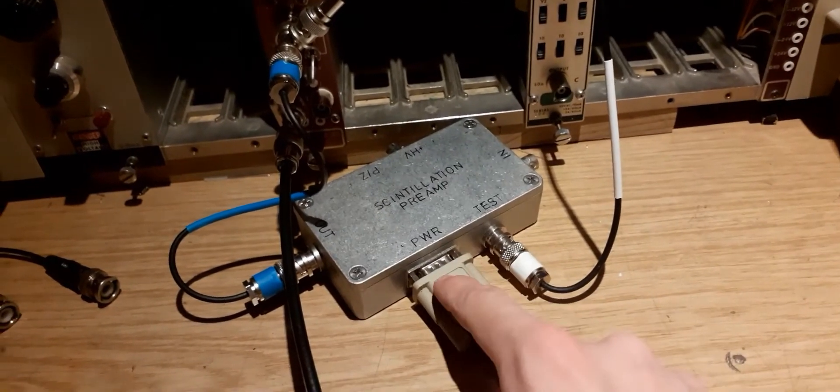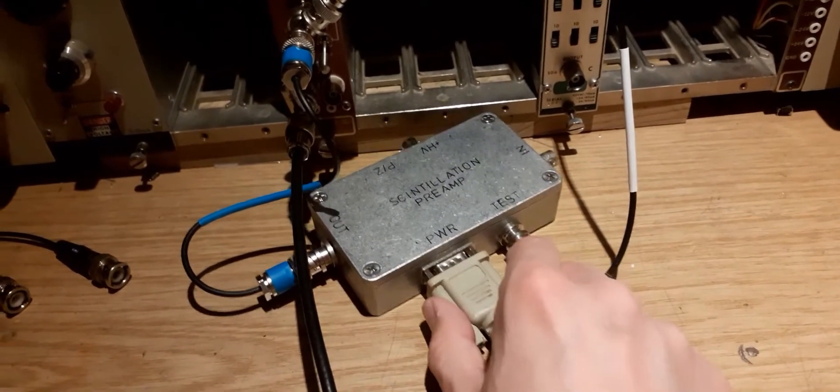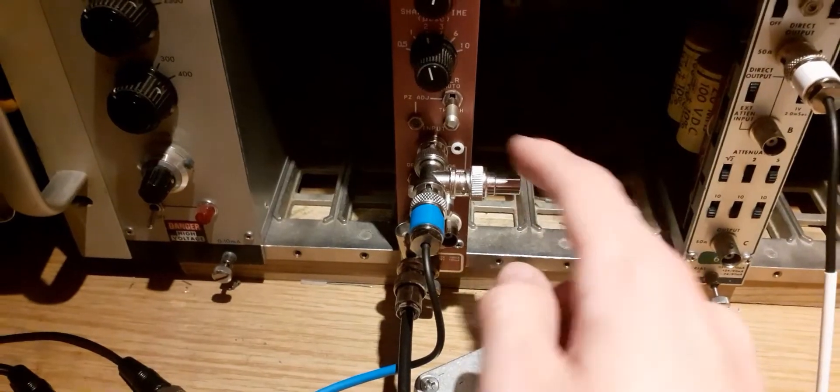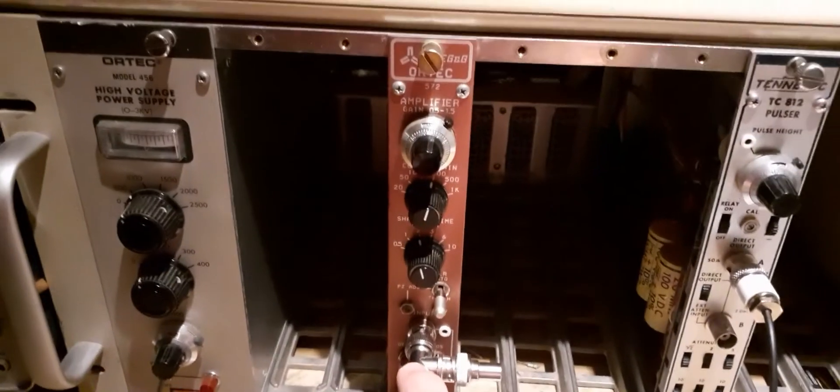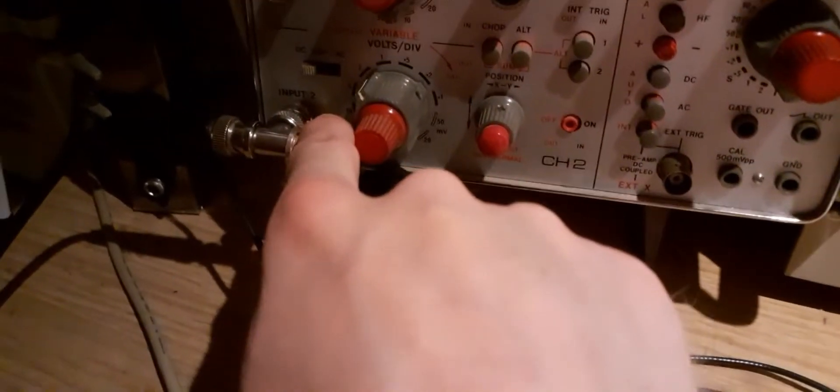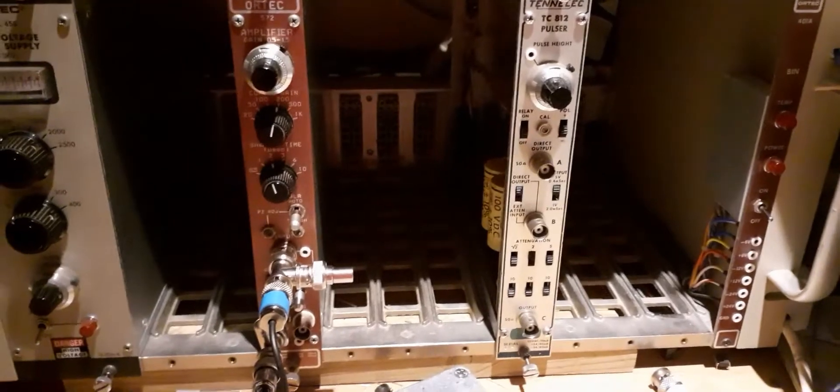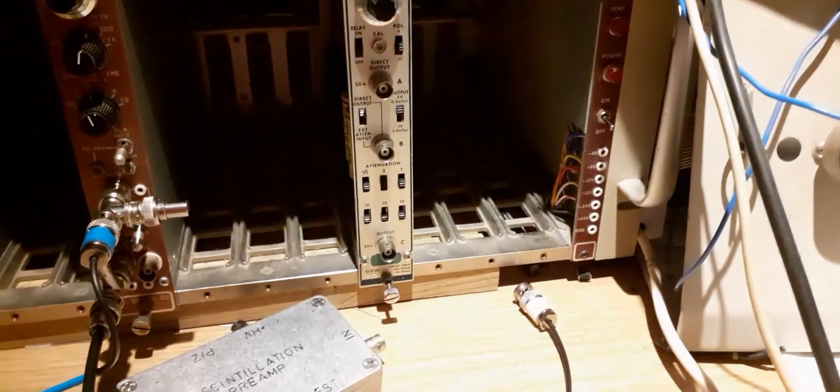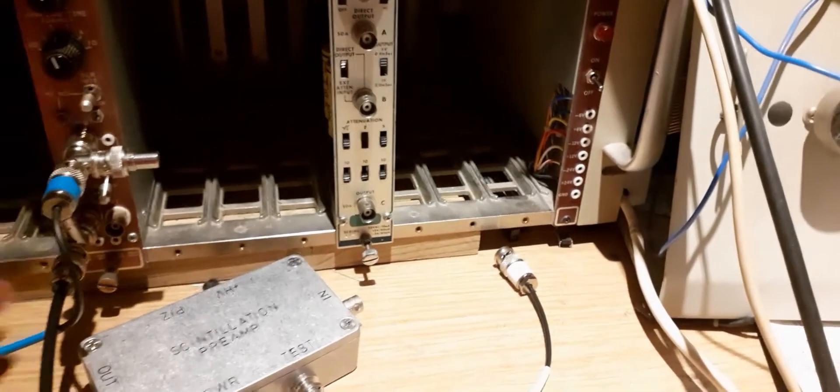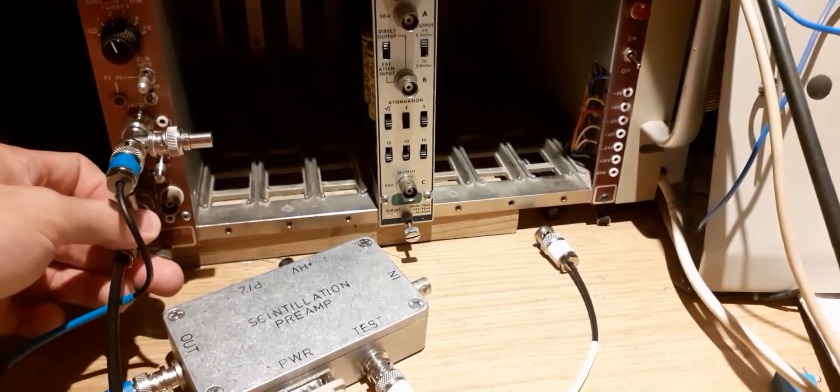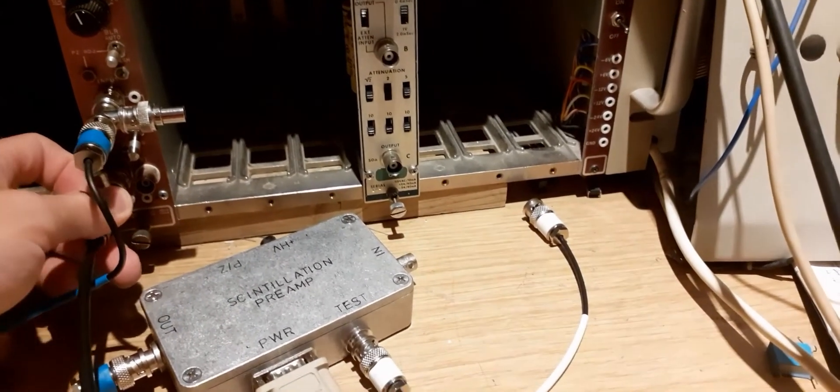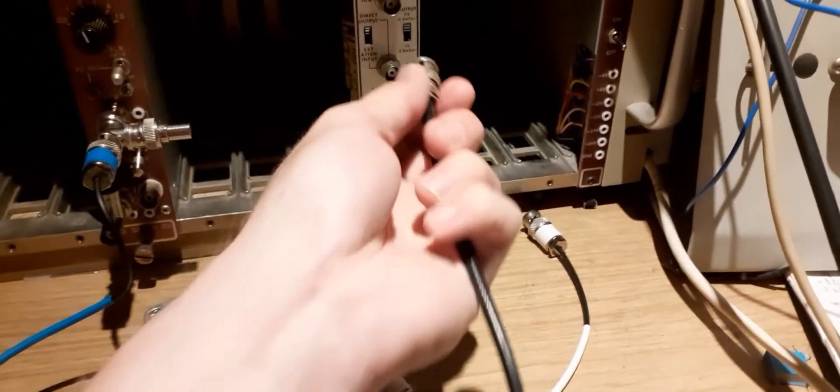So the signal path is: pulse generator to preamplifier (the preamplifier is getting power from the bin), preamplifier out directly into the input of the spectroscopy amplifier, output of spectroscopy amplifier going to scope and going to a PC card down here, which is running a multi-channel analyzer. First of all, let's take a look at the output from the actual pulse generator. Normally if this was a detector you would have to use the preamplifier and buffers, but since this is a pretty low impedance signal we can actually just connect a cable directly to our scope.